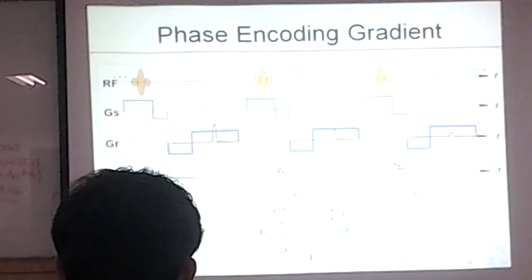So generally we use the alternating order of phase encoding steps from 0, increasing or decreasing, because the zero phase encoding signal has the maximum signal. So we first get the largest signal, then if there are some problems later, we can generally reconstruct the image even though it is poor.